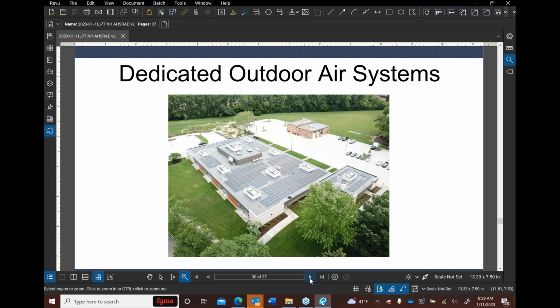You can see the no-fly zones on the roof where the PV panels couldn't go because of shadows, where they were inefficient. So that was a challenge. That's why we ended up having to land panels over on the maintenance building, which you can see in the background of this image across the parking lot. We talked to the ICCF, the organization giving the grant, and they were accepting of this, that we just didn't have enough roof area to meet the energy demand. We talked to the village. They would not accept ground mounted panels from a zoning perspective. So we ran conduit underneath the parking lot, which was replaced as part of this project too. So it was open and connected the PV panels on the maintenance garage to the building system.